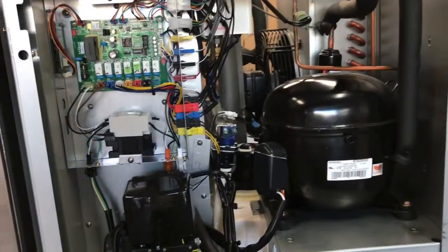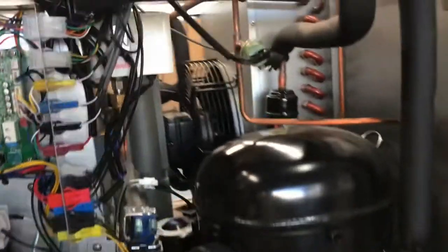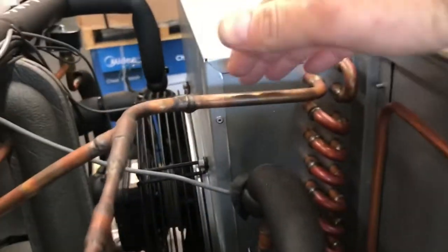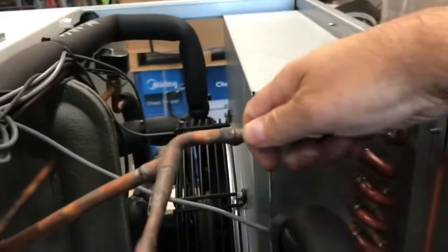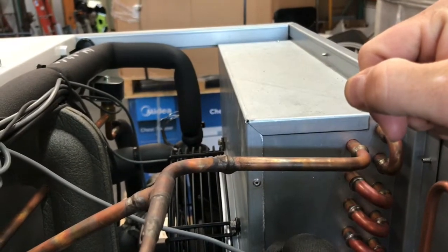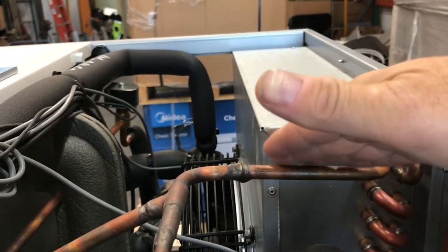If you get to a machine and your pressures are off, you're gonna have to start feeling around. So you're gonna come over here to your inlet on your condenser and you're gonna feel it. You're not gonna just grab onto it like this. You're gonna kind of do this and feel it, because it's gonna be so hot that it's gonna burn your hand. So you're gonna touch it and just go, okay, yeah, that's really hot. And then you're gonna move down to where it's exiting down there at the bottom, and you're gonna reach down here and feel this.